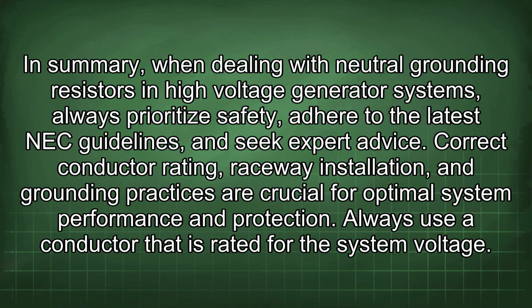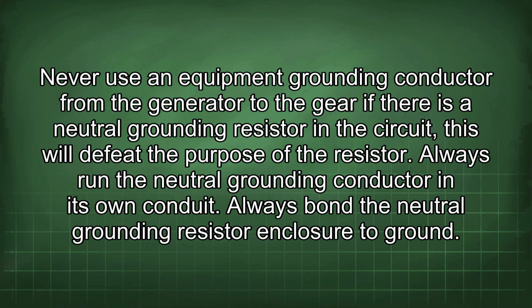In summary, when dealing with neutral grounding resistors in high-voltage generator systems, always prioritize safety, adhere to the latest NEC guidelines, and seek expert advice. Correct conductor rating, raceway installation, and grounding practices are crucial for optimal system performance and protection. Always use a conductor that is rated for the system voltage. Never use an equipment grounding conductor from the generator to the gear if there is a neutral grounding resistor in the circuit. This will defeat the purpose of the resistor.